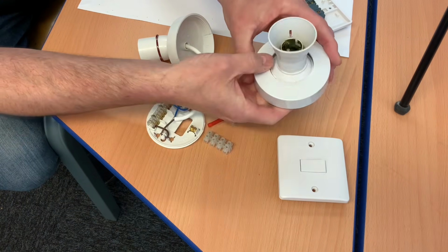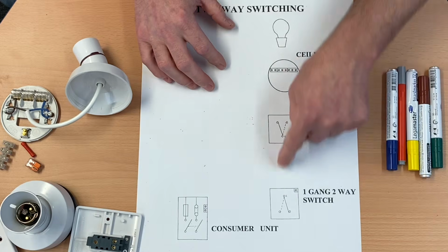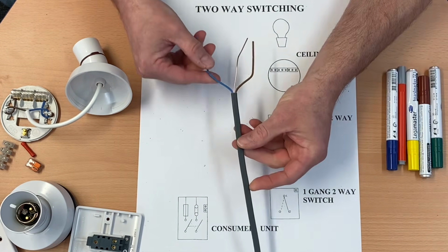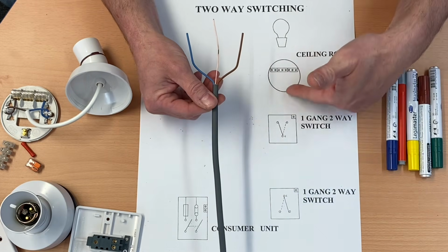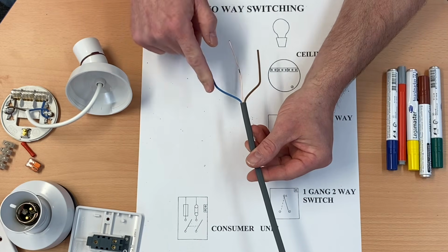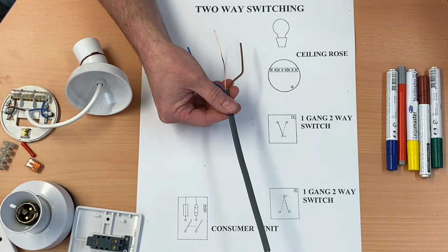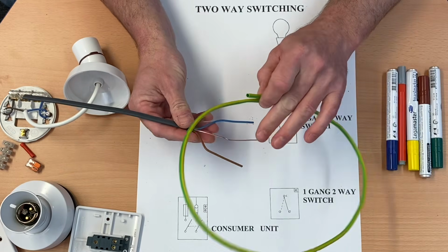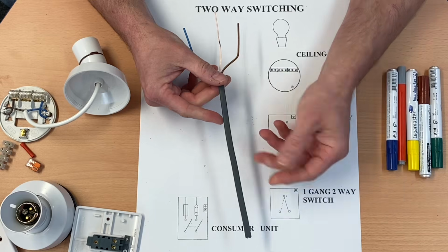We're looking at how we're going to make our connections for a wiring diagram to help us do two-way switching of a light fitting. We're going to be using, again, PVC twin and CPC cables. I know in the past at college I have used twin brown, and I talked about it in the first video down to the switches, but I'm going to keep using twin and CPC. So we've got a brown, a blue, and a circuit protective conductor, which we'll identify on the drawing with green and yellow, to identify the green and yellow sleeving that would go on top of that for identification purposes. It's 1mm squared at my college, it might be 1.5 in the real world.